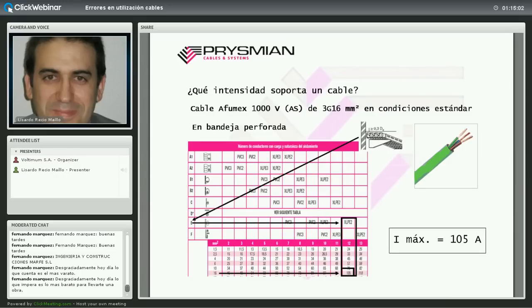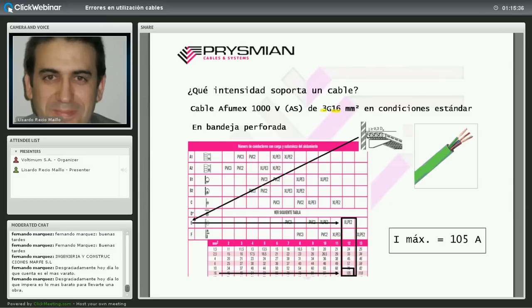Ejemplo: cable AFUMEX 1000 V, 3G16. Tiene tres conductores de 16 mm² (marrón, azul, amarillo-verde), dos conductores activos (fase y neutro). Si está en bandeja, el sistema de instalación es E (bandejas con cables multipolares). Entramos por E hasta la columna XLPE2 —dos conductores cargados, cable termoestable de 90 grados— y para sección 16 la tabla de la UNE 20460-5-523 nos da 105 A de intensidad máxima.